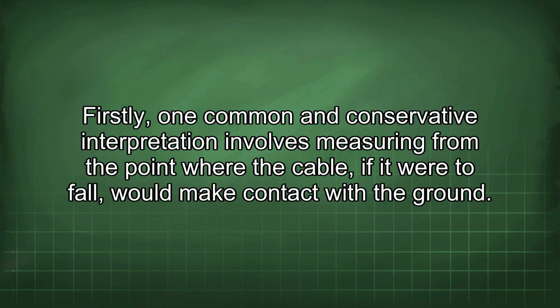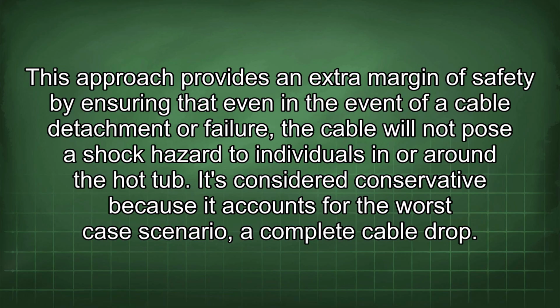Firstly, one common and conservative interpretation involves measuring from the point where the cable, if it were to fall, would make contact with the ground. This approach provides an extra margin of safety by ensuring that even in the event of a cable detachment or failure, the cable will not pose a shock hazard to individuals in or around the hot tub. It's considered conservative because it accounts for the worst-case scenario, a complete cable drop.